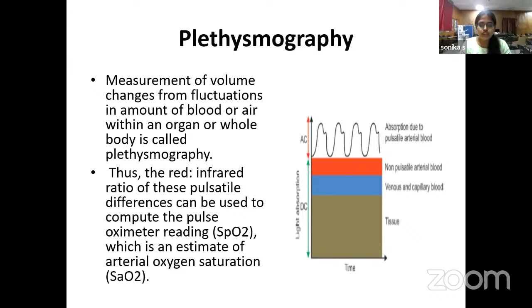Absorption of light passing through a tissue is characterized by two components. One is the AC component, another one is the DC component. The AC component is the absorption due to pulsatile arterial blood, whereas the DC component contains non-pulsatile arterial blood, venous and capillary blood, and also tissues. Thus the red and infrared ratio of these pulsatile differences can be used to compute the pulse oximetry reading, that is SpO2, which is an estimate of arterial oxygen saturation.